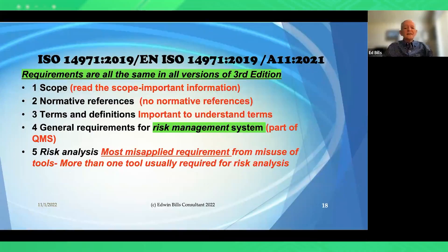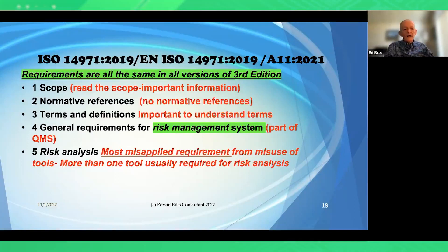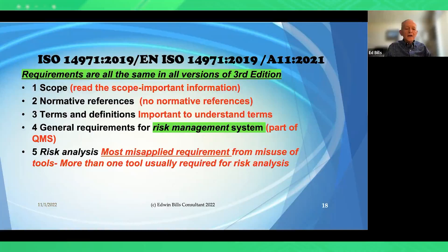Risk analysis is the most misapplied requirement and the most common area for misuse of tools. There is more than one tool required to do a good risk analysis. There are newer tools for usability-related risk analysis, which are better than use-FMEA. Multiple tools should be applied. Probably the most important is preliminary hazard analysis (PHA), which can be done as early as the research phase, before design controls are even applied.